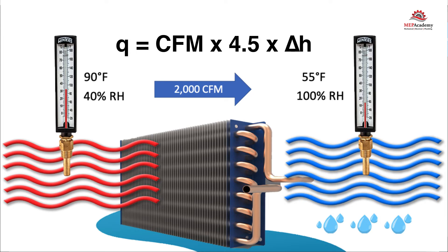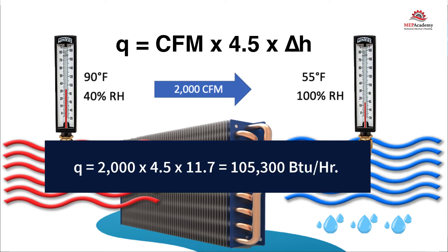We get Q equals 2,000 times 4.5 times 11.7 equals 105,300 BTUs per hour.